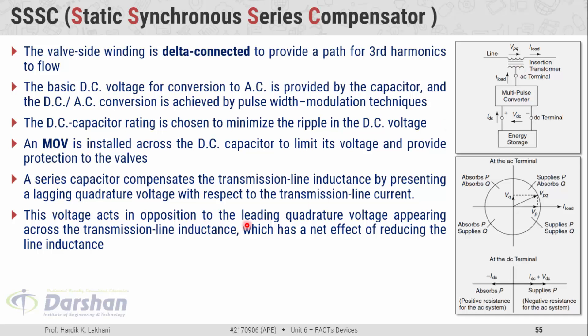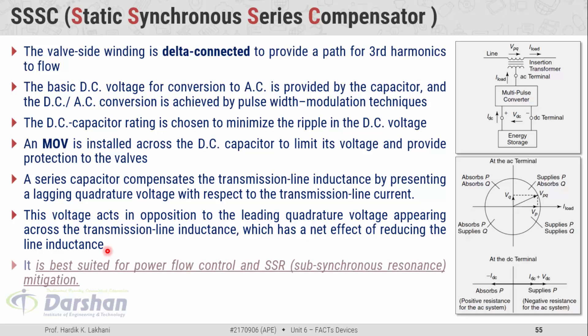This voltage acts in opposition to the leading quadrature voltage appearing across the transmission line inductance, which has the net effect of reducing the line inductance. A series capacitor compensates the transmission line inductance by presenting a lagging quadrature voltage with respect to the transmission line current. Primarily, the Static Synchronous Series Compensator is used for two purposes: to control the power flow, and for mitigation of sub-synchronous resonance.